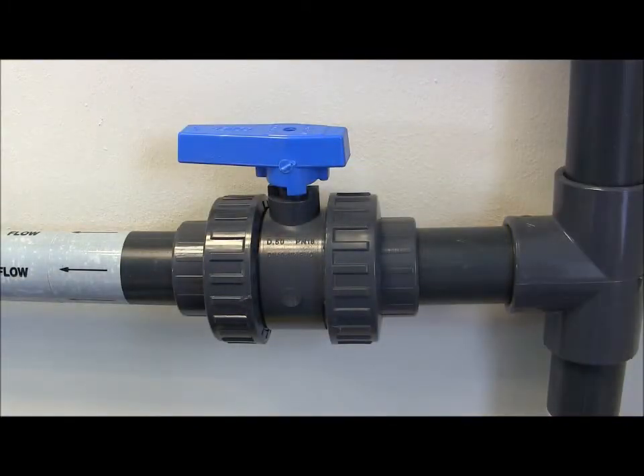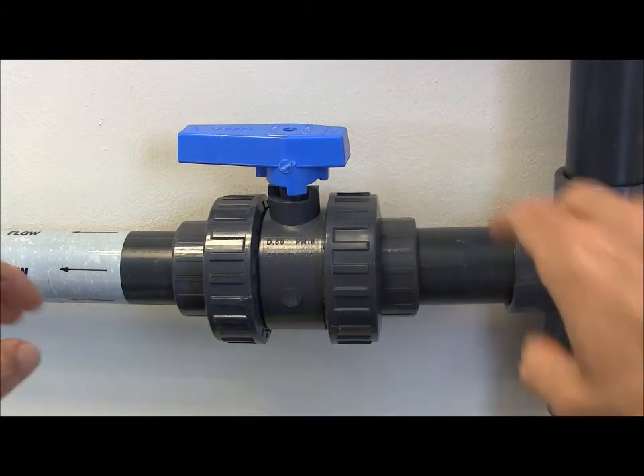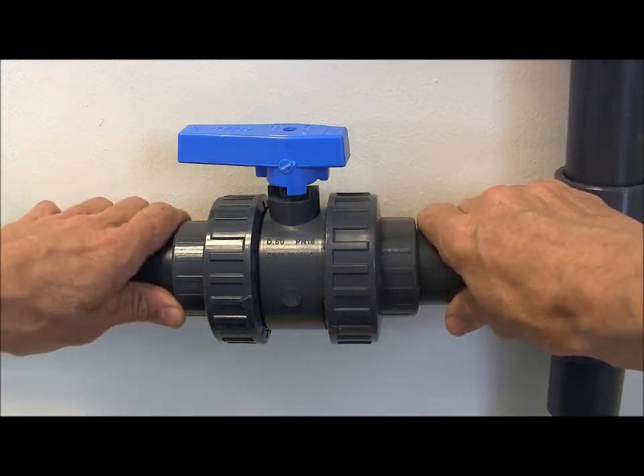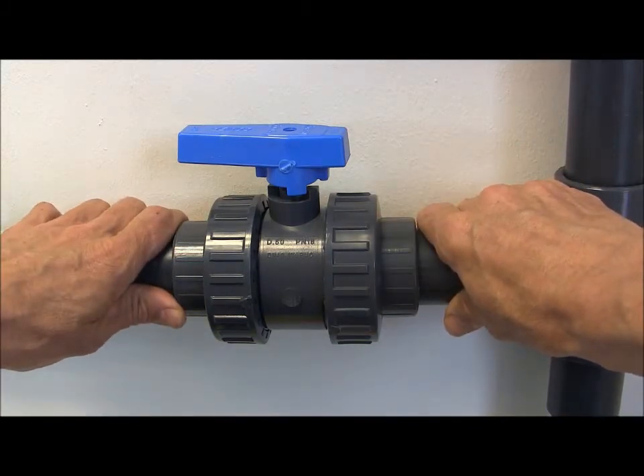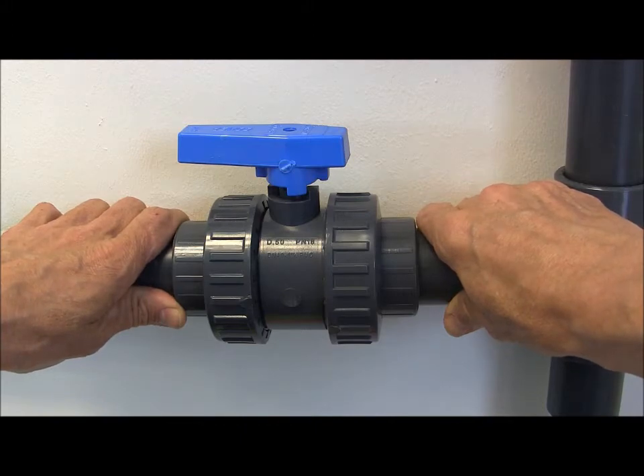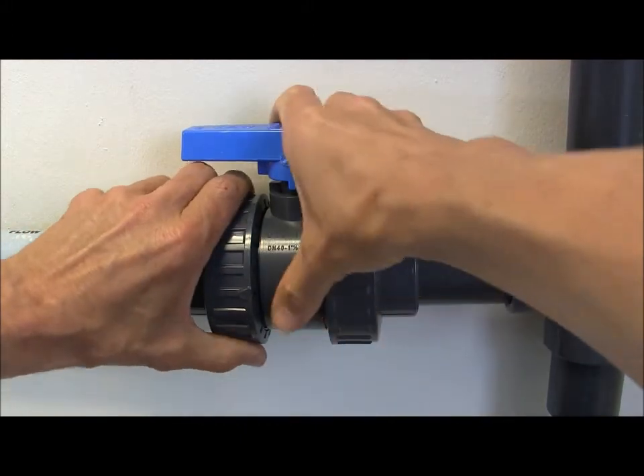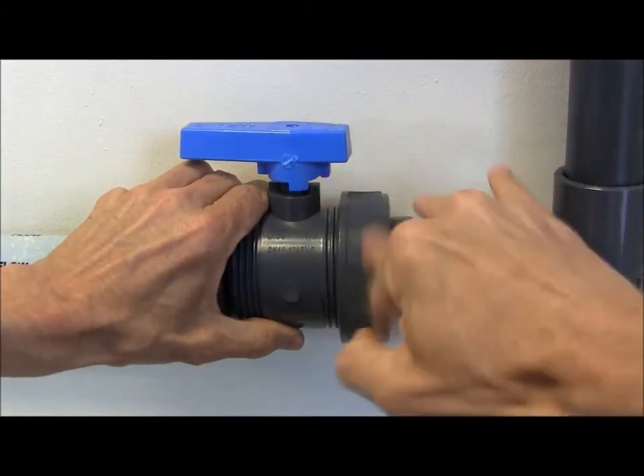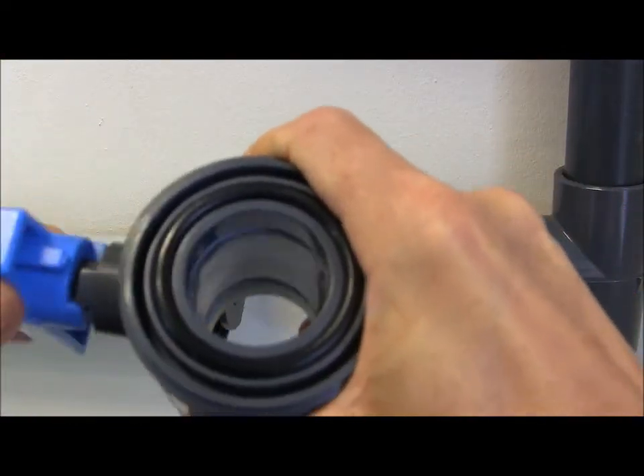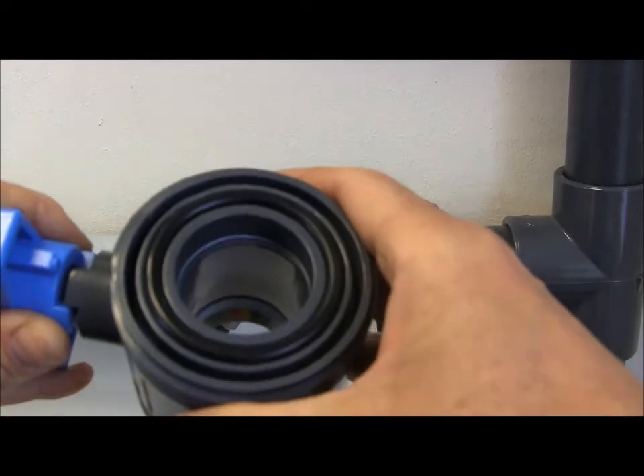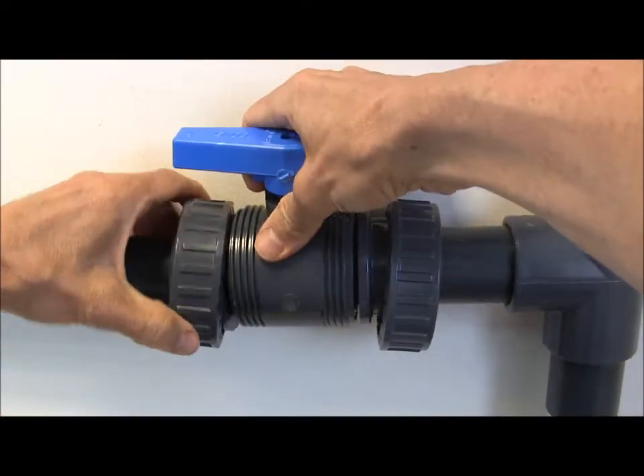Double union ball valves are generally used in pipe systems where there is a fixed pipe coming in and a fixed pipe which is going out from the valve. In this situation if the valve needs servicing or cleaned or if there's a blockage in the line the valve can easily be removed. It can be checked for operation, the seals can be checked. If need be parts can be replaced or indeed the whole valve body can be replaced before reassembly into the line.